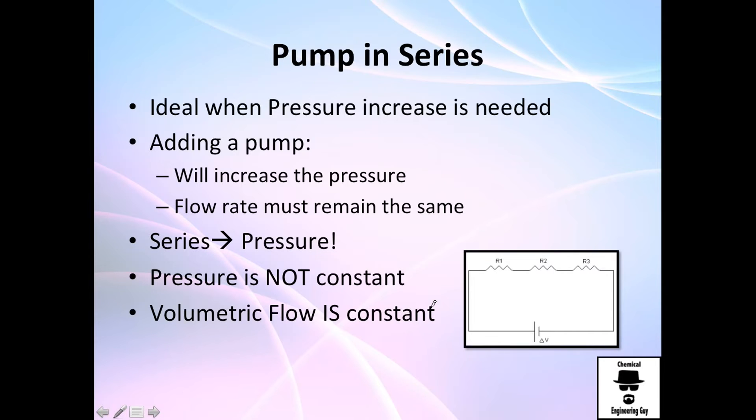But what will happen if we choose pump in series? It's ideal when pressure is an important parameter. We want to increase it, so this is the best option. If you want to increase pressure, you need to use series arrangement. Adding a pump will increase the pressure, and the flow rate remains the same.